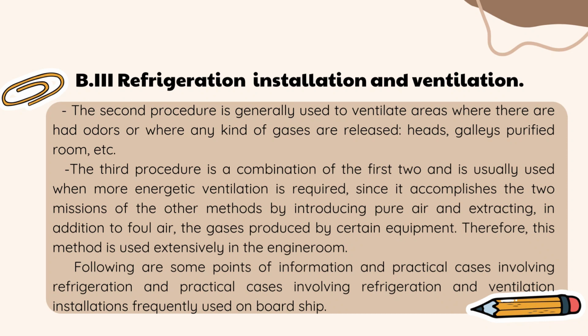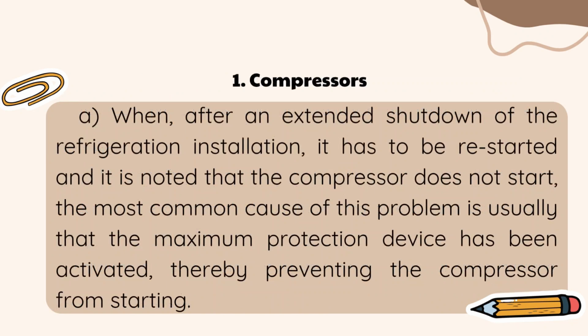Following are some points of information and practical cases involving refrigeration and ventilation installations frequently used on board ship. 1. Compressors. A. When, after an extended shutdown of the refrigeration installation, it has to be restarted and it is noted that the compressor does not start, the most common cause of this problem is usually that the maximum protection device has been activated, thereby preventing the compressor from starting.